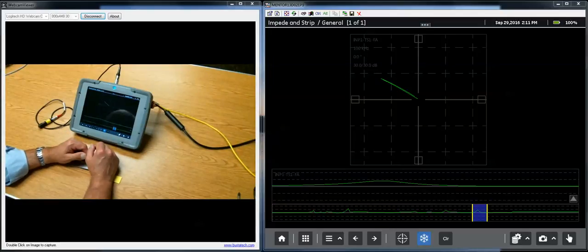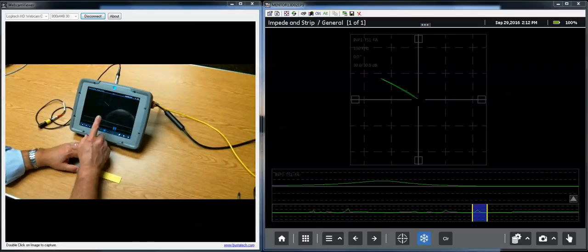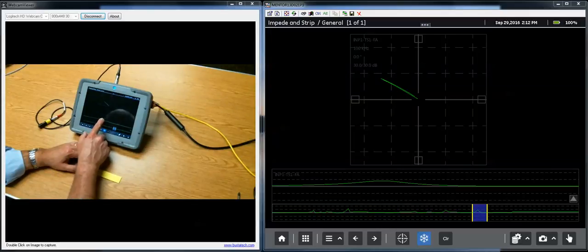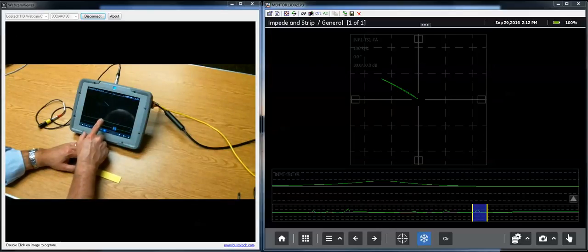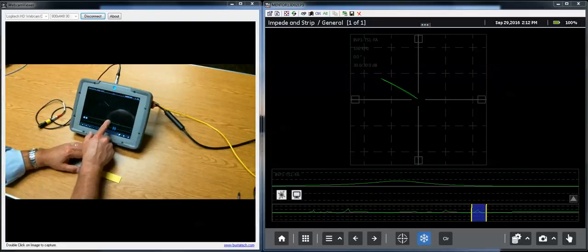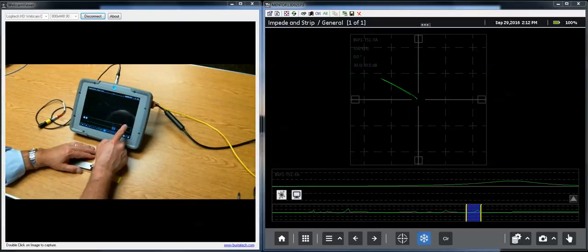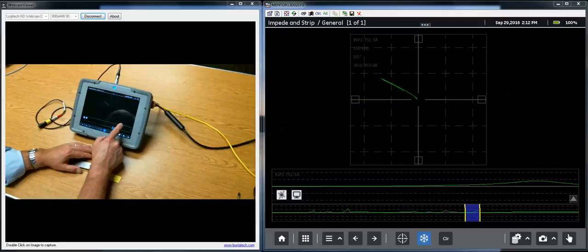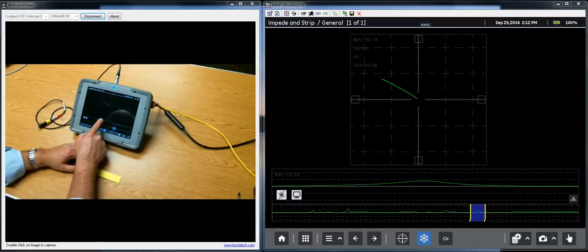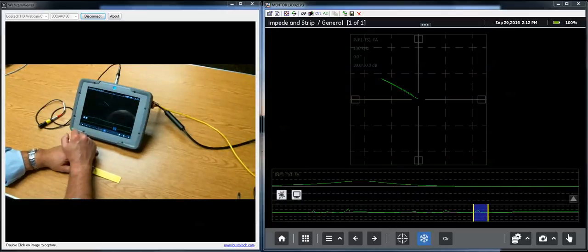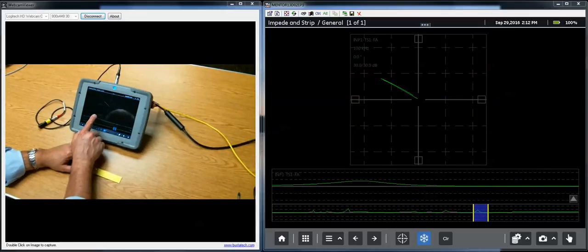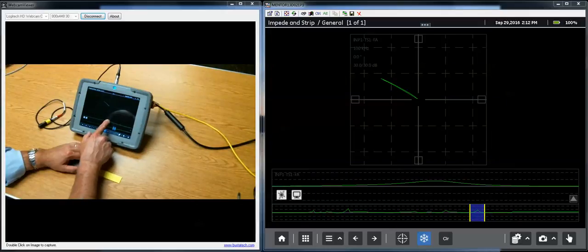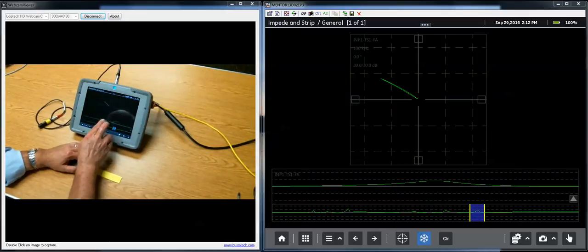So again, that's I put my finger down, that starts a cursor. I drag my finger, the cursor gets wider or narrower. I lift up, now my cursors are in place. At this point I can take my finger, go to the top part of the strip chart. If I put my finger down there and swipe it from side to side, you'll notice my cursor box moves together. So one finger touch, move side to side, I can center that trace.